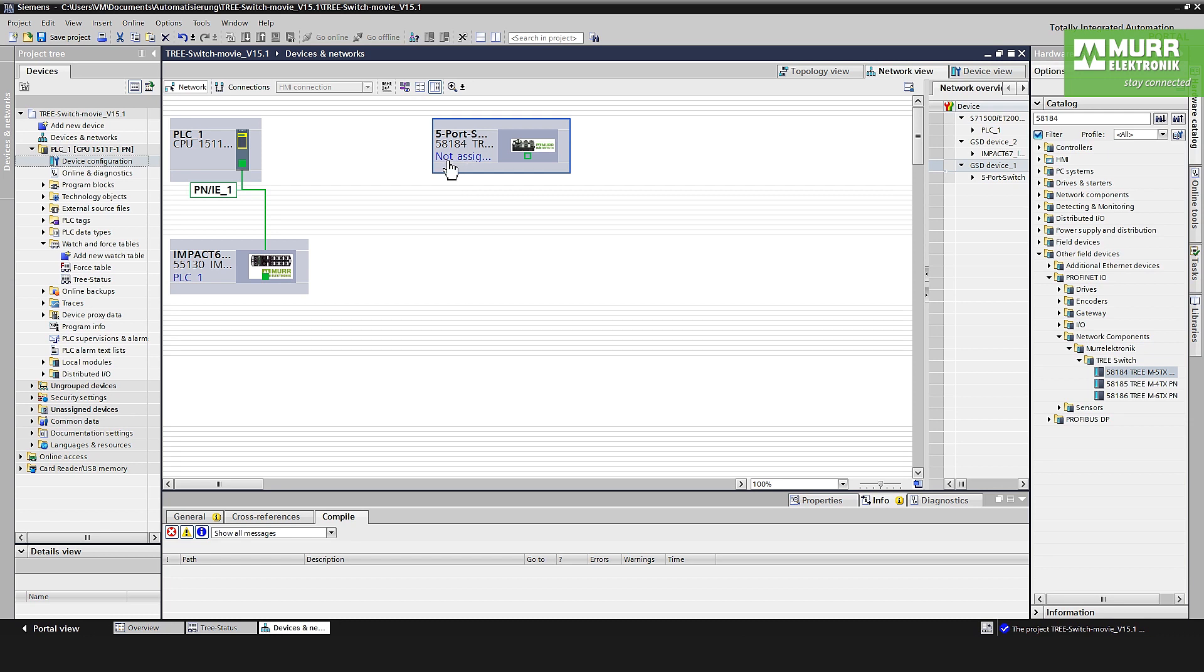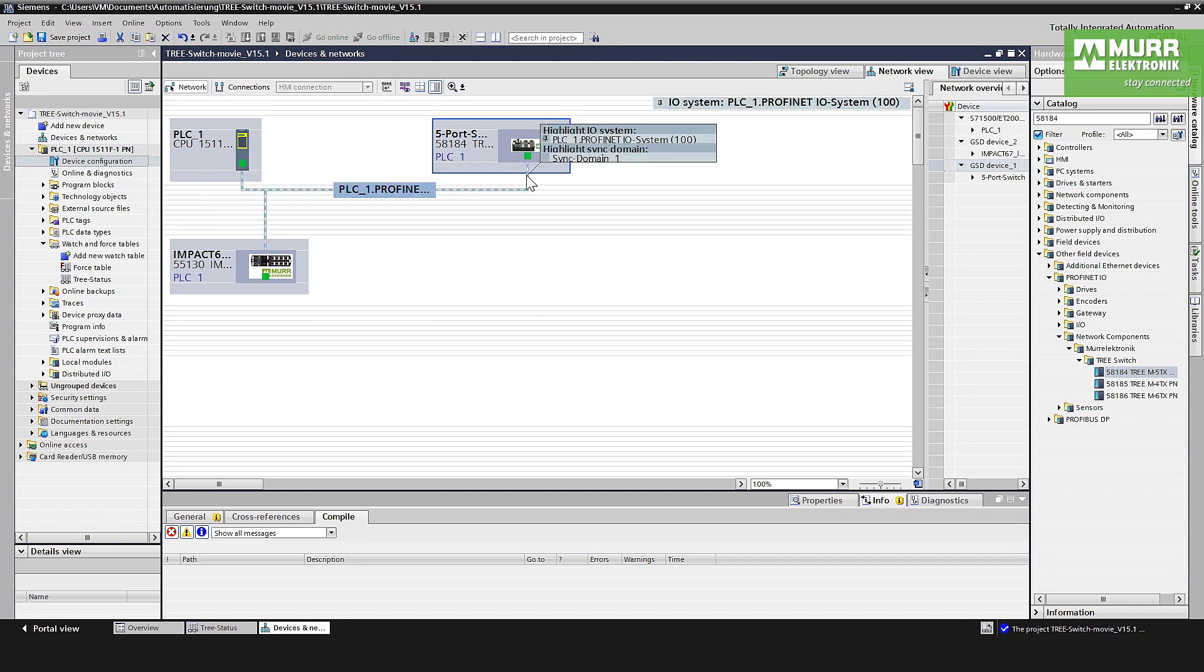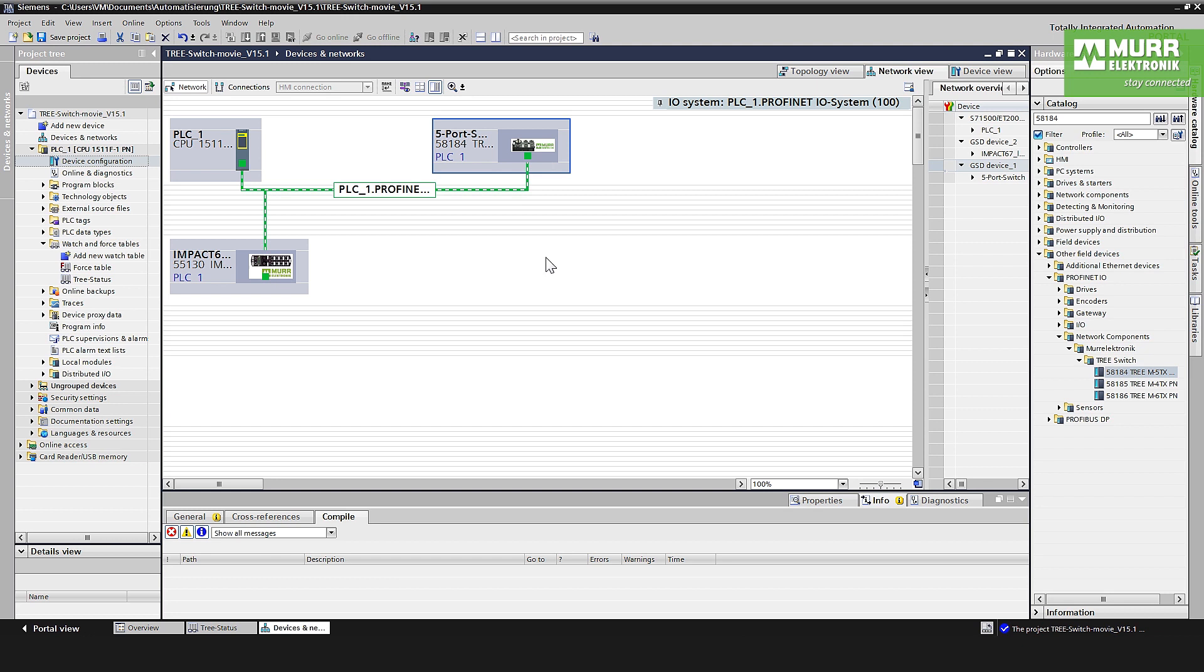To connect the switch to the PLC, you see here it's not assigned. You have to assign the switch, click on the yellow and the blue one, select the Profinet interface. When the green line is connected between PLC and switch, the switch is fully integrated into the hardware configuration.